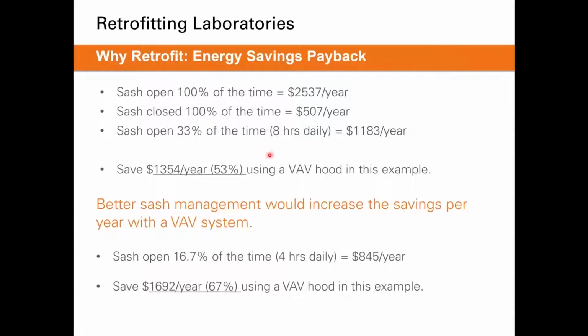So I made some assumptions on the sash open percentage time. Taking those numbers from the calculator, if it was open 100% of the time, that would equal a cost of $2,500 per year. If the sash was closed 100% of the time, that would equal an operational cost of $500 per year. But if we assume that the hood is open 8 hours daily, so 33% of the time, that comes out to around $1,180 per year. So we went down from $2,500 to $1,180 by swapping out our constant volume hood with a hood that could turn down when the sash is being closed. That afforded us 53% savings by swapping to a VAV hood for this example.